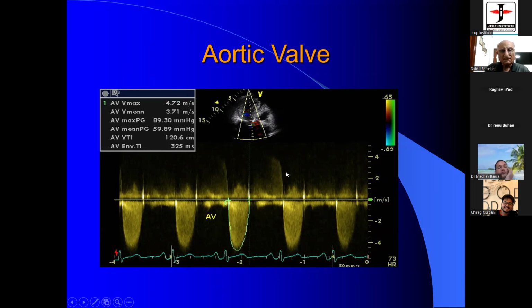If your velocities are wrong, then all your results will be wrong. That is why we'll tell you later on, when you come for a particular valve, we always take multiple views to say which view gives us the maximum possible velocity. So the only thing to remember is to try to get a maximum velocity: a low velocity by pulse Doppler, a high velocity by CW.